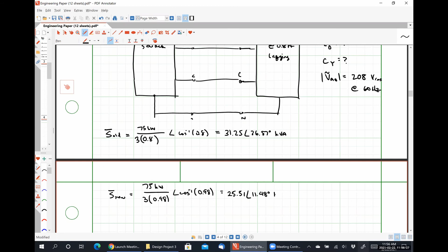Our new complex power is going to be 75 kW divided by 3 times 0.98, with an inverse cosine of 0.98. Please tell me what that gives me. 25.51 at an angle of 11.48 degrees, kilovolt amperes. Alrighty.